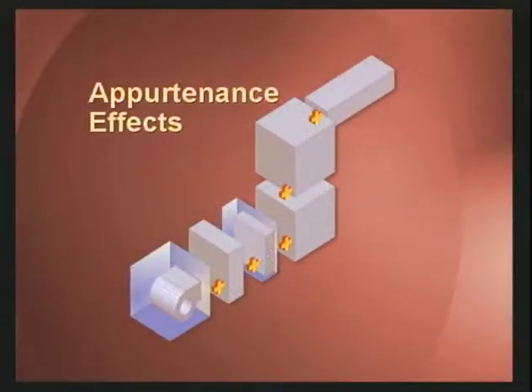Specifically related to appurtenance effects, let's take a look at a figure that shows you a little bit of what I'm talking about. Appurtenances can be anything from modulation devices on the fan, such as inlet guide vanes. It can be downstream or upstream modules or cabinets. It can be coil sections or filter sections. Or it can be supply plenums, or even in some cases, application elbows or ductwork, as long as they're defined.